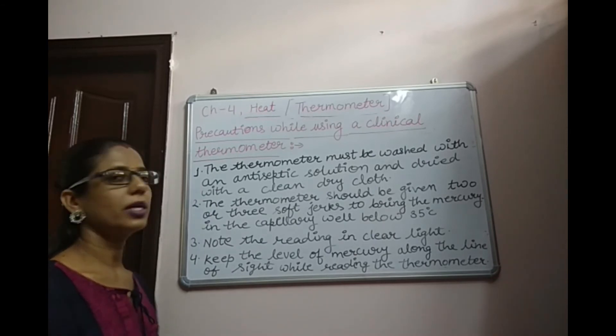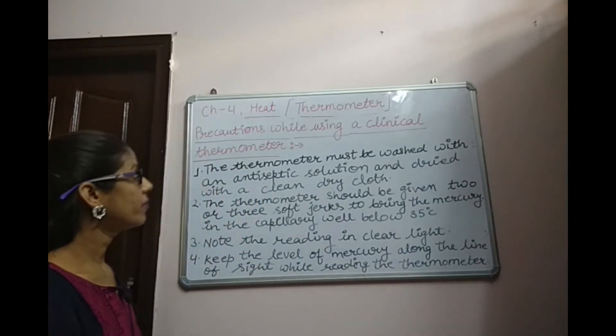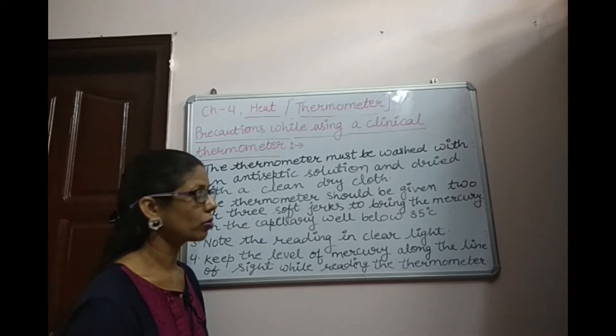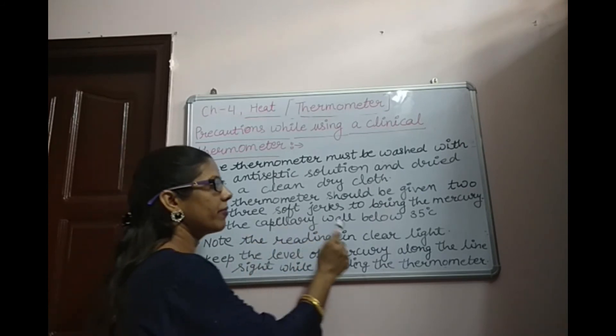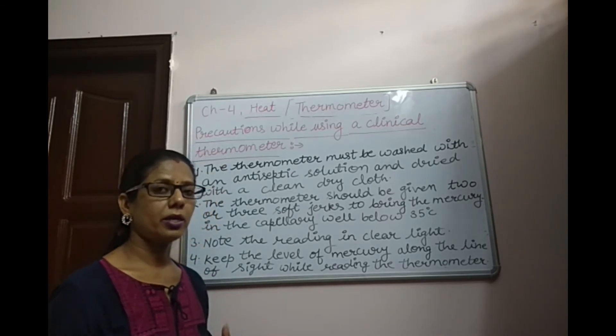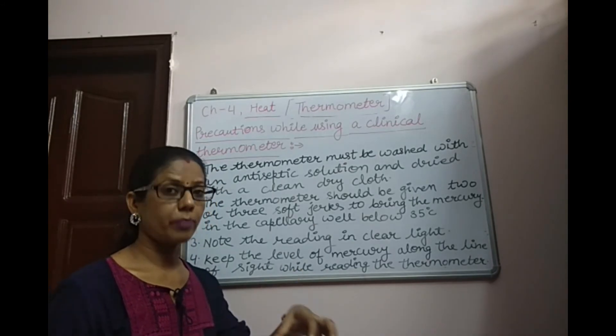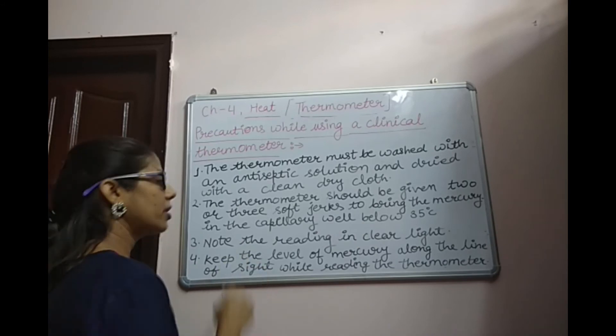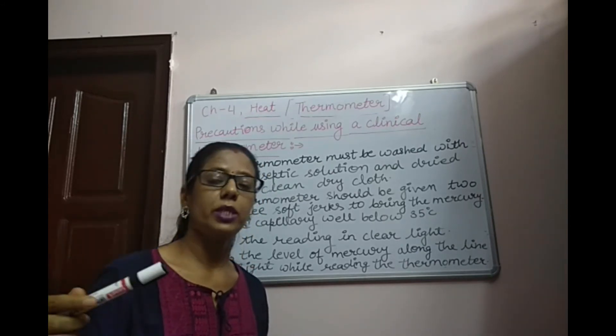Our next topic is precautions while using a Clinical Thermometer. First, the thermometer must be washed with an antiseptic solution and dried with a clean cloth before and after every use. Second, the thermometer should be given 2 or 3 soft jerks to bring the mercury in the capillary well below 35 degree Celsius. While giving the jerks, the thermometer should not hit any hard object, because it can break.